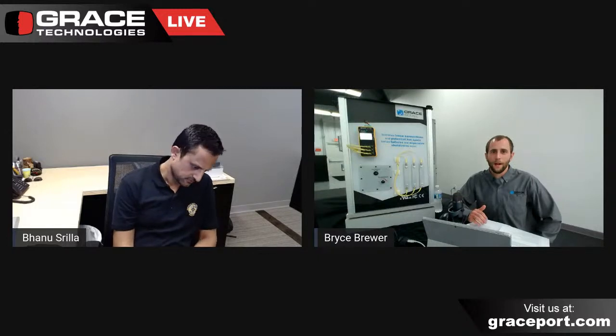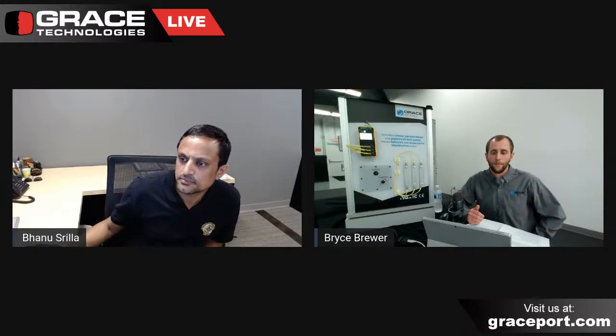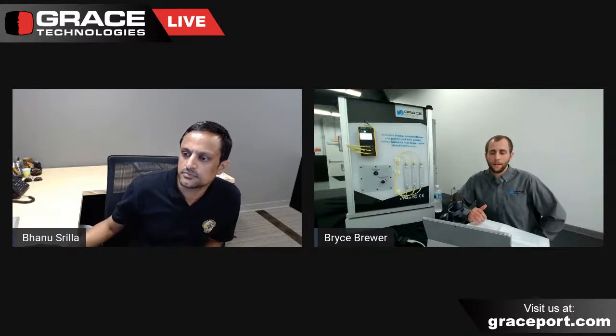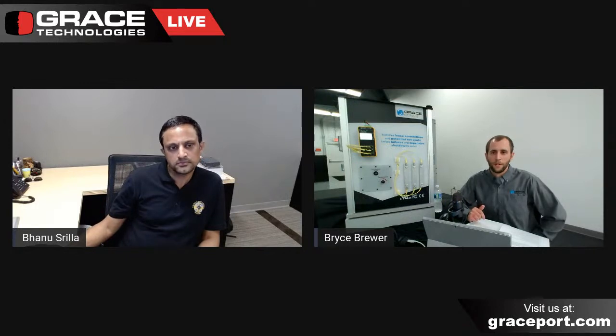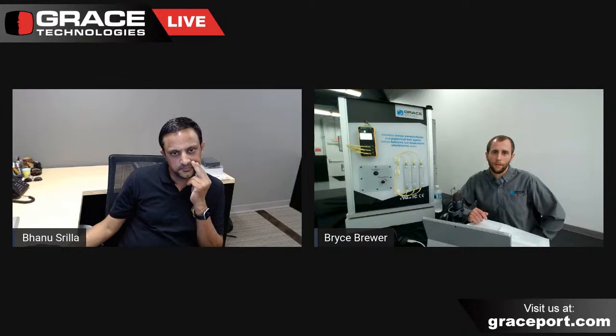That's a very good point. I'd say definitely don't throw away any of your IR equipment, because this is really a complementary package with your IR program. I wouldn't try to outfit an entire facility with this type of equipment. Really it comes down to a criticality analysis, making sure your key points that you couldn't live without are monitored. That's where we'd say to start. That doesn't mean that on auxiliary power distribution, if you already have your IR window there, you shouldn't continue those inspections. We'll tackle the key ones with the hotspot monitor to get that on a continuous basis, and then potentially expand. It doesn't mean you have to do one or the other—it works really well in a complementary relationship.